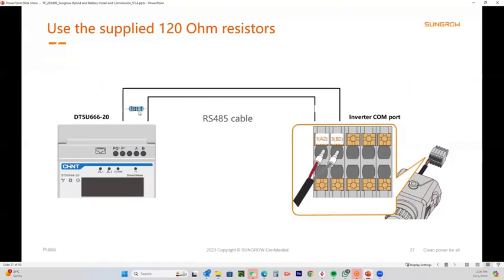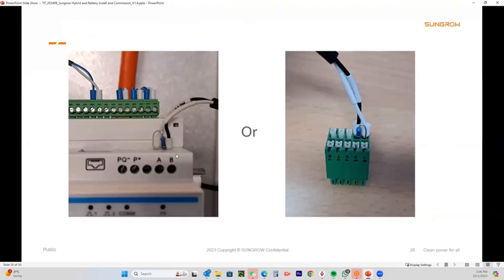You will also get in the box these little 120 ohm resistors. The purpose of the resistor is called a termination resistor, and what it does is it stops data reflections in the cable, so it's going to improve signal quality. So I do recommend that you do that. If you don't do it and you're getting problems with dropouts, put it in anyway. It'll only take you 5 seconds, and you basically just bend it over and put it in like that. You can do it at this end, at the plug, but that end is a lot easier at the meter.